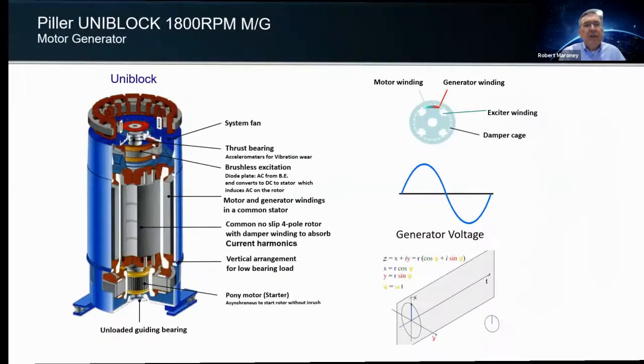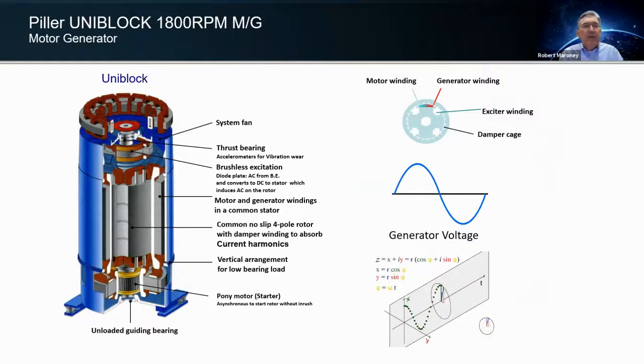So the next part is going back to talking about the motor generator. The uniblock is what we call it, and this is our power conditioning component we've been talking about. As we talked about, in the top right corner you can see where we have the motor winding and the generator winding unified into the same stator. Then you have an excitation winding, and a damper cage around the system, all surrounded by a stator. On the left, this is what it would look like in total.